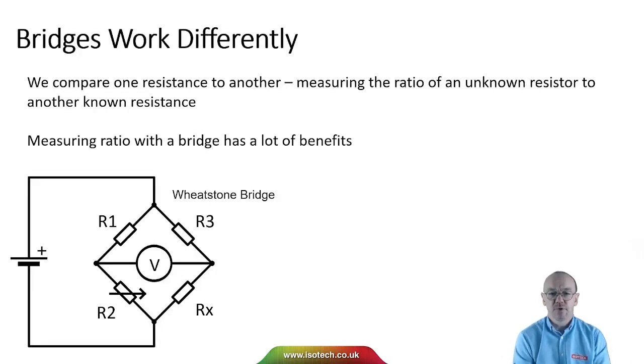So bridges work differently. We compare one resistance to another. By measuring the ratio of an unknown resistor to a known resistance, we get a lot of benefits. The gain errors will drop out, other things will disappear, and we're able to make measurements much better than 1 part per million, down to perhaps 20 parts per billion, or maybe even slightly better.